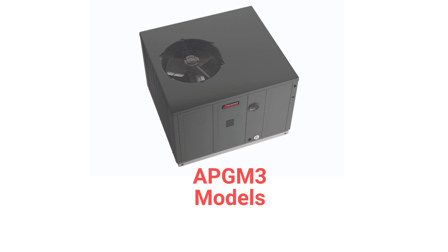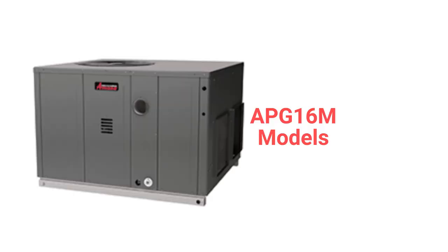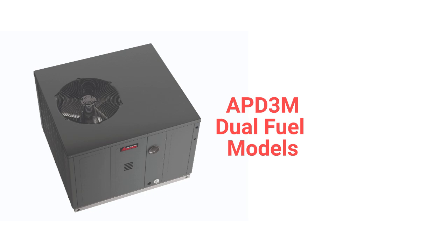The APGM3 model combines a basic single-stage 13.4 SEER2 efficient air conditioner with a single-stage 81% AFUE gas furnace, while the APG16M units have a two-stage compressor with 16 SEER cooling efficiency and an 81% efficient gas furnace. The APD3M model is a dual-fuel packaged gas furnace with a 13.4 SEER2 cooling efficiency, a 6.7 HSPF2 heating efficiency for the heat pump, and a two-stage 81% AFUE gas furnace.